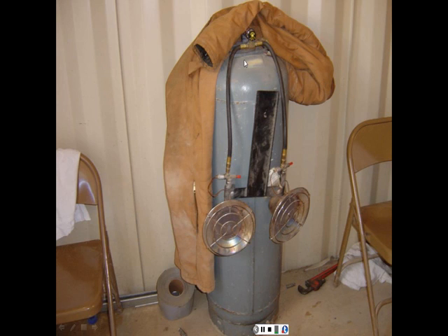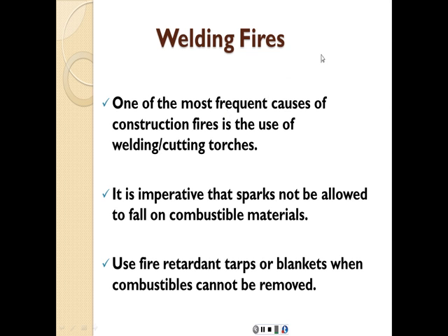Another violation here, we have a coverall stored on top of a gas tank. So this is flammable. We have here curtains, it seems like curtains or something like that. That probably could also be flammable. And some other clothing here. So that's not the proper storage.